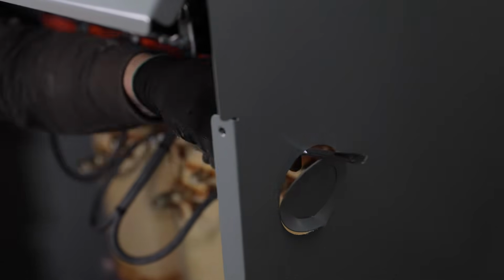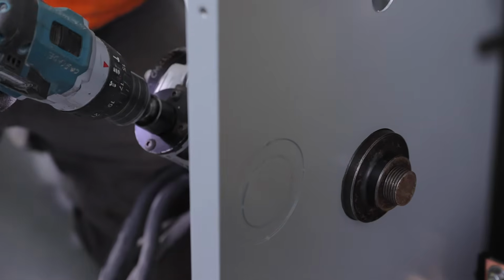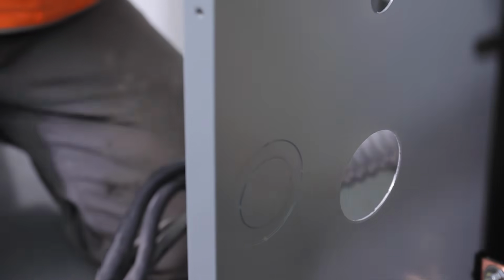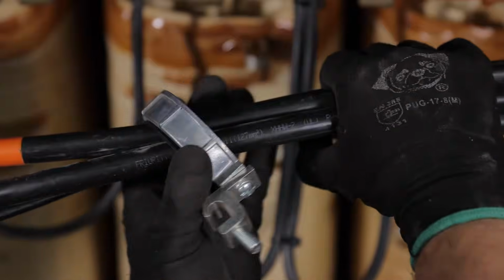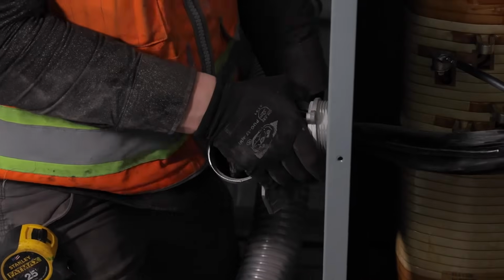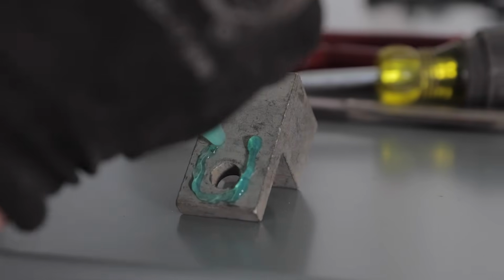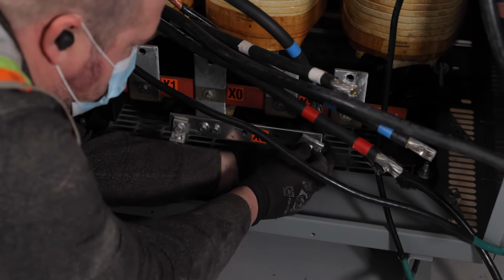Conduit holes are then punched into the sides of the case using either the factory-provided knockouts or put in manually using a hole punch. The cables are then fed into the transformer case, and the flex conduit is attached to the sides. All wires are connected via mechanical lugs, with NOALOX applied where the connection is made.